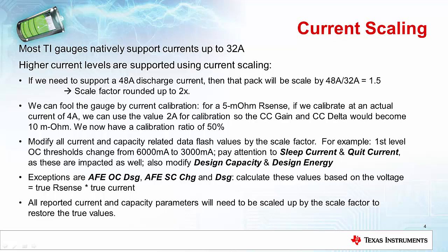In order to do this, you do need to modify all the current and the capacity related data flash values by the scale factor that you're using. That includes the first level overcurrent thresholds, which have to go down from 6 amps down to 3 amps, and a lot of settings like sleep current, quit current, design capacity, and design energy. There are a few exceptions which are related to the hardware protections in there. Those you want to leave based on settings that are like true RSense times your true current for the protection level that you're trying to implement.